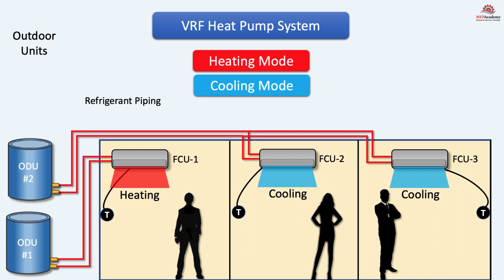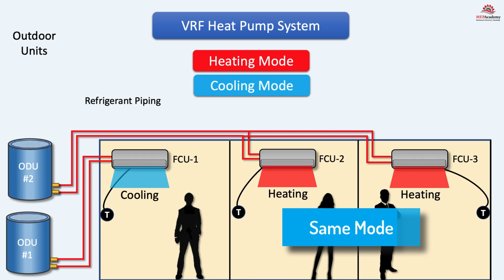Now, whenever fan coil number 2 and 3 switch modes of operation, they will always be in the same mode as they're on the same outdoor heat pump system, as shown here now in heating mode together, while the outdoor unit number 1 can be any mode separate from the other system.